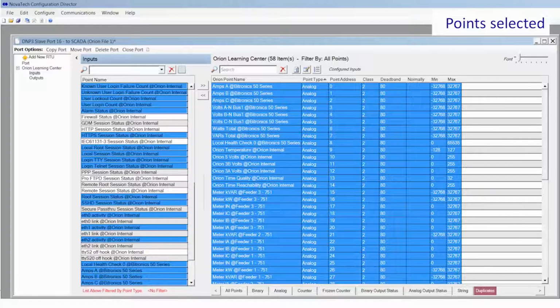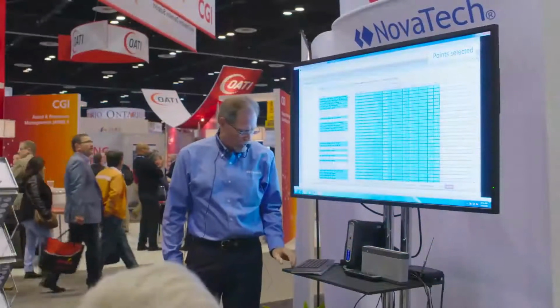Once again, I set some common defaults, but if I need to go in and change those, change scaling factors, change deadband, I can select all the points, do a common attributes, change it one place, and it changes all of it for me. I don't have to go in and change it individually.